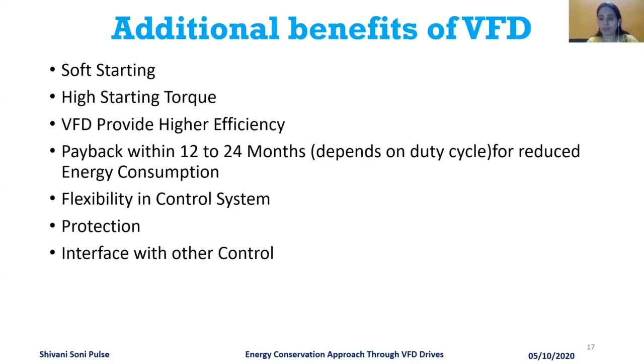Obviously, we get the payback within 12 to 24 months, because as per the duty cycles we have reduced the energy consumption. If we reduce the energy consumption, we get more payback. Flexible control is also there, because they have a PID controller and many monitoring parameters. Protection relays are also provided on the VFD systems, and it can interface with other control systems. So if we use the VFD in industry, we can definitely control our power consumption for today's industrial automation sites.